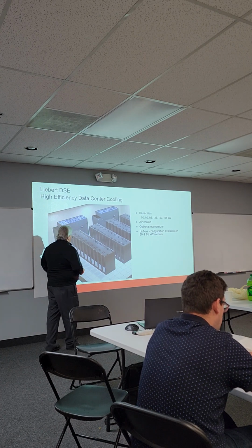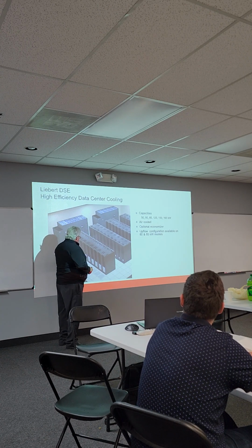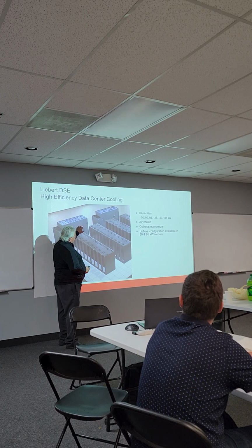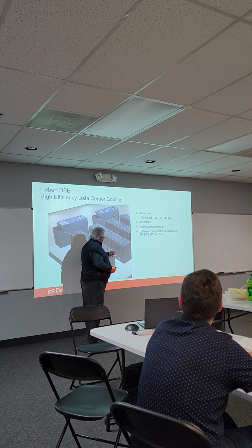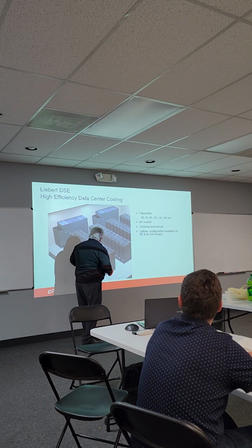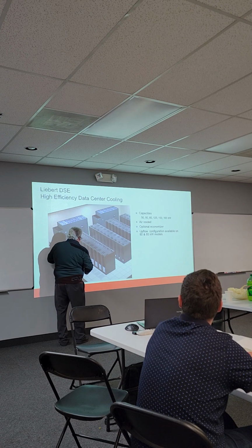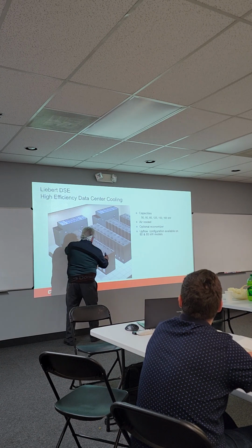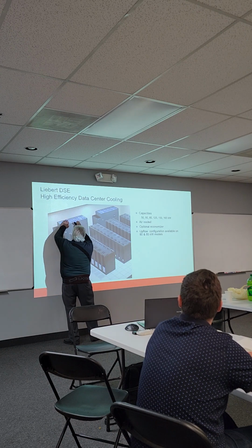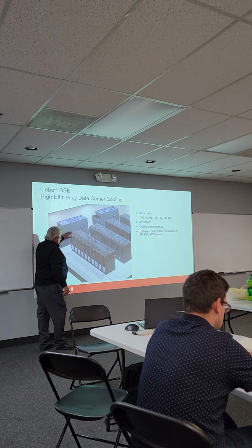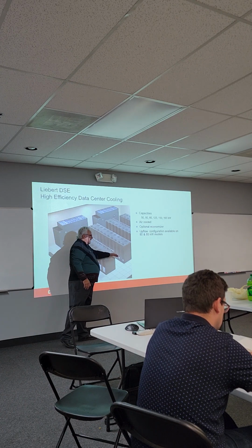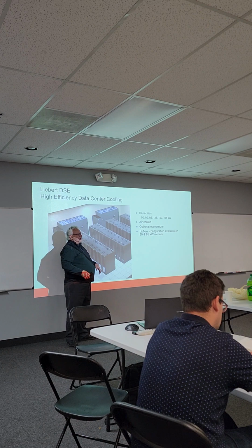What most people get wrong in computer rooms is how they lay out the racks and where they actually position the air conditioners. In this case, you see they have the perforated tiles on the sides, which is pretty good. And this would be what they consider a hot aisle. The servers go in from the front, as shown there, take air in from the front, exhaust out the back, and then the heat goes back to the return. So that would be a typical cold aisle, hot aisle. And that's how we want to set up rooms.